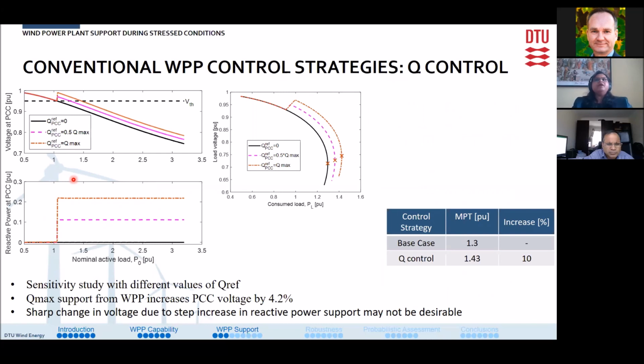As mentioned before, no specific control action from wind power plant is specified during stress condition. So here we assume that the conventional control strategies as described during normal operation will be applied during stress condition as well. With this in mind, we do a sensitivity study for Q control strategy for different values of reactive power references. And we compared the results with the base case of zero reactive power support, that is unity power factor control. So there is no exchange of reactive power between the wind power plant and the grid.